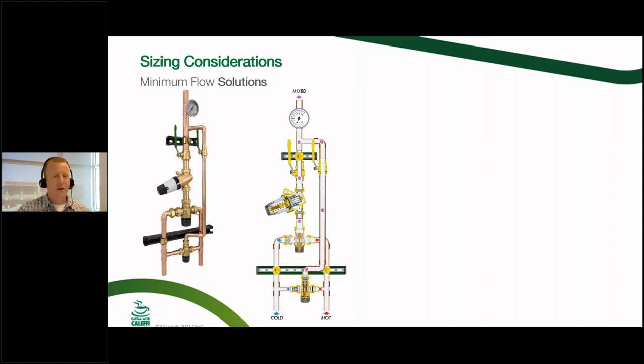Now, what's great about this scenario is that this big mixing valve here can handle 40 gallons a minute at a maximum. This little guy here can only handle 10. But the difference is that this big guy up here has a minimum flow of 4.4, which is obviously not attainable in many cases with a single lav or multiple lavs, but this little guy down here has a minimum flow requirement of 1 gallon per minute. So now you actually have the ability to have accurate control from 1 gallon per minute all the way up to 50 gallons per minute with this high-low assembly. And these are very common. This is not abnormal or anything like that, but this is another one of those scenarios where it's just a little bit different, and you're going to have to set these up properly, just like the recirc that we were talking about before.